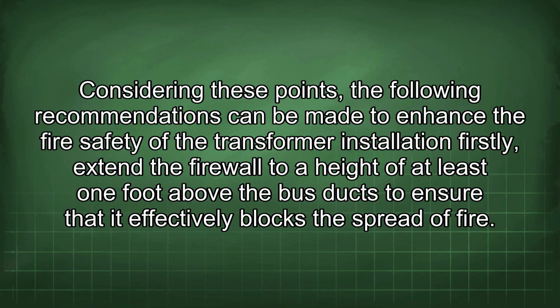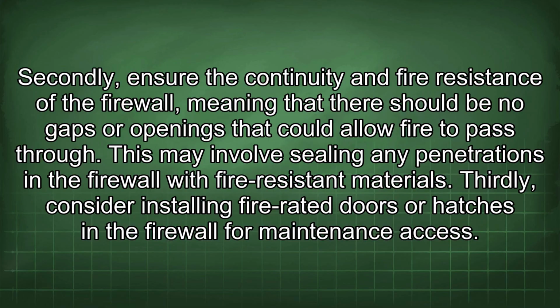Considering these points, the following recommendations can be made to enhance the fire safety of the transformer installation. Firstly, extend the firewall to a height of at least 1 foot above the bus ducts to ensure that it effectively blocks the spread of fire. Secondly, ensure the continuity and fire resistance of the firewall, meaning that there should be no gaps or openings that could allow fire to pass through. This may involve sealing any penetrations in the firewall with fire-resistant materials.